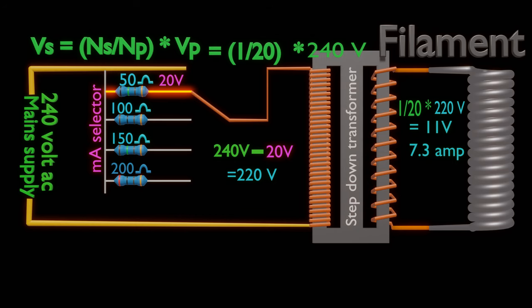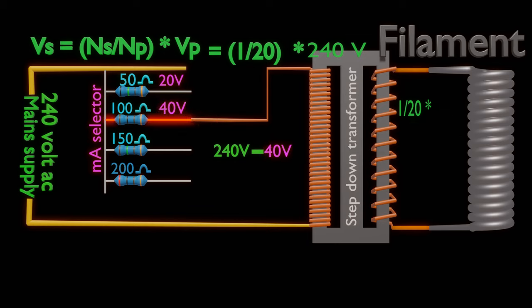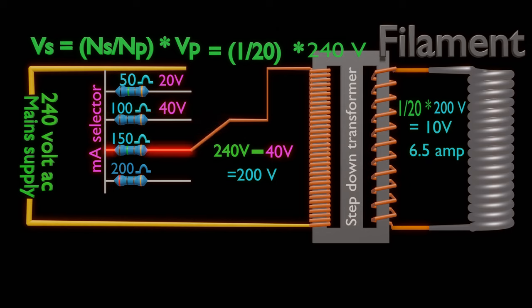Let's switch to 100 ohm resistor. Let there be a voltage drop of 40 volts across the resistor. Voltage available across primary winding will be 200 volts. Voltage across secondary will be 10 volts. Let's say it leads to a filament current of 6.5 ampere. Similarly, with switching of other two resistors, we can alter filament current to a certain value.